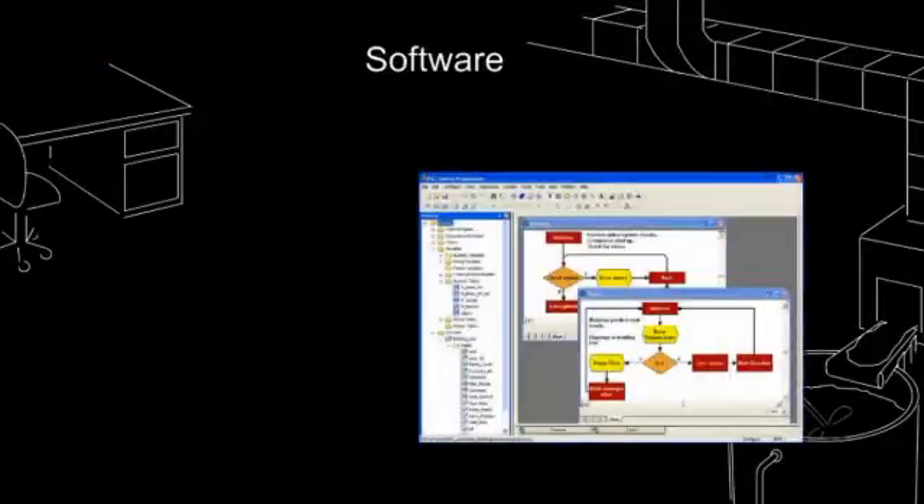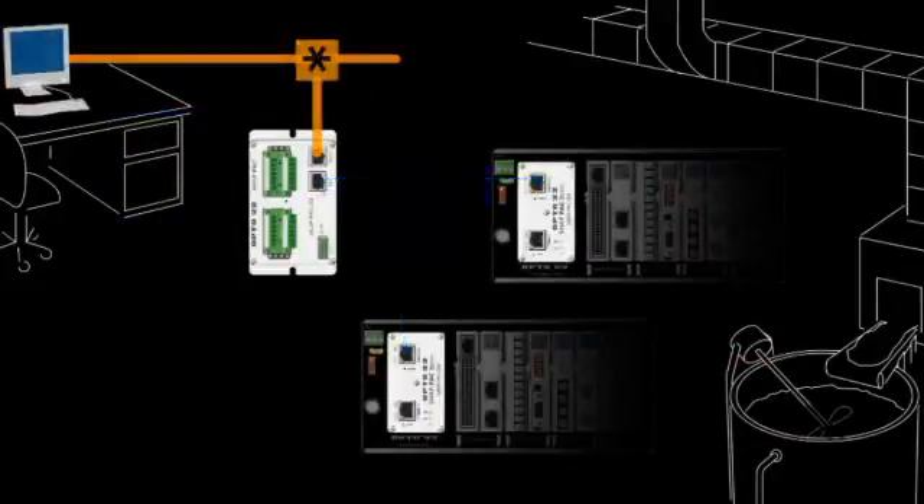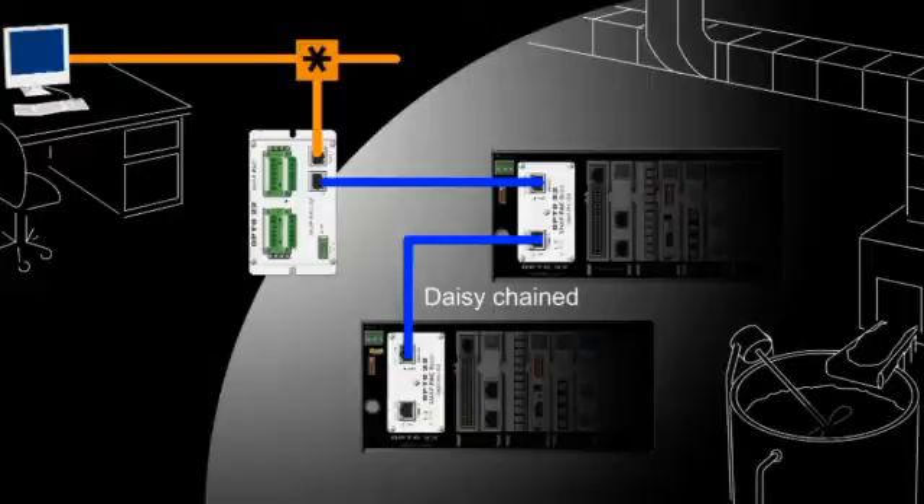To use these advanced features on SNAP PAC controllers, you'll need PAC Project Professional. On SNAP PAC I.O. brains, however, the dual interfaces are connected and together act as a built-in Ethernet switch. This means you can daisy-chain or multi-drop I.O. brains over Ethernet without the need for external switches.